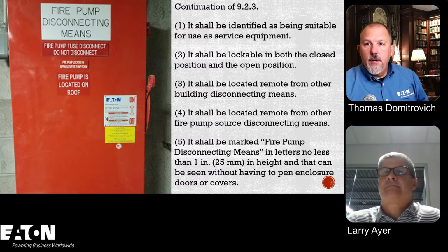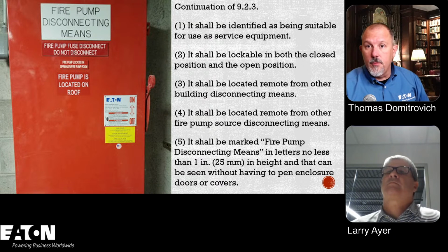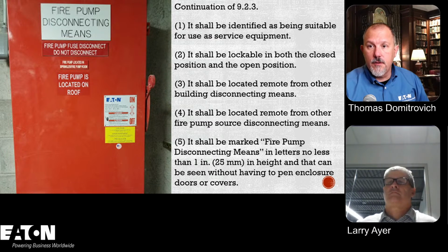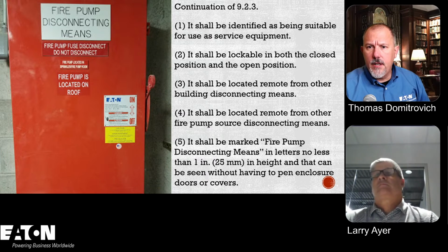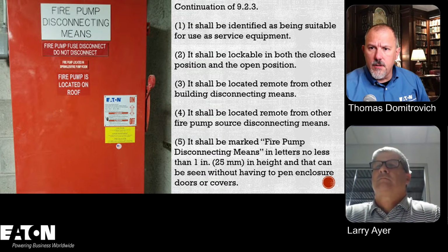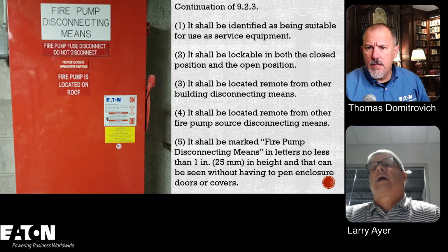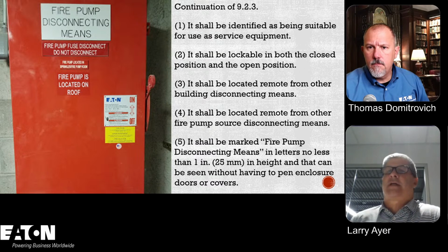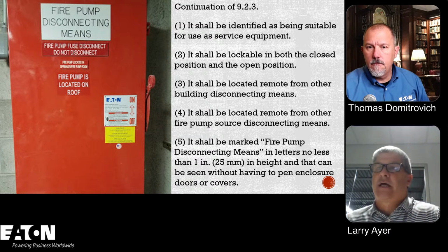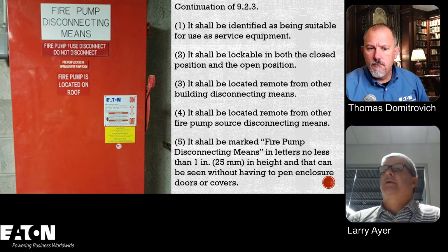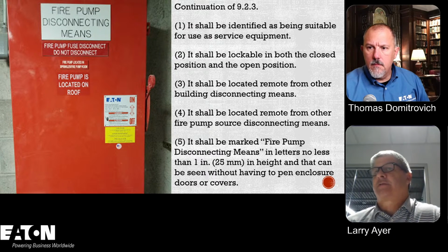All right. So we're continuing in Chapter 9.2.3. If it's service equipment, it obviously has to be identified as suitable for use as service equipment, or suitable only for use as service equipment, I guess depending on how it's designed. Correct. These are the requirements for the disconnecting means, and that disconnecting means could be the fire pump controller. Whether that disconnecting means is tapped off the service or it's a fire pump controller, it has to be suitable for use as service equipment.